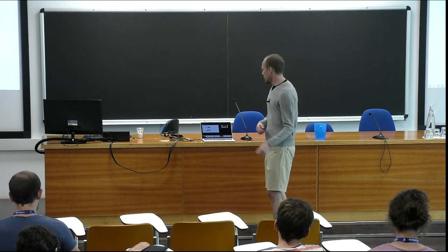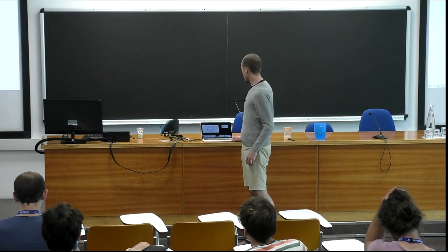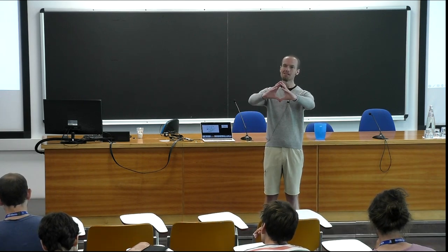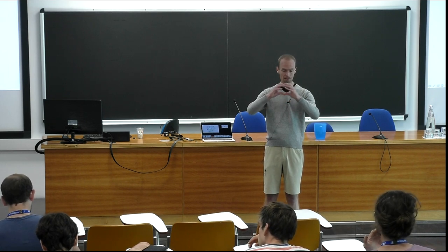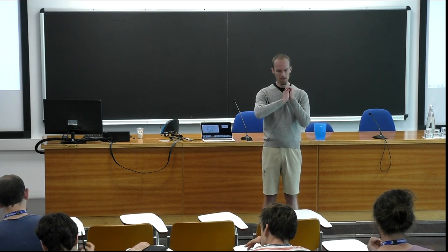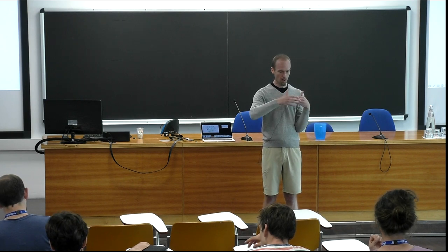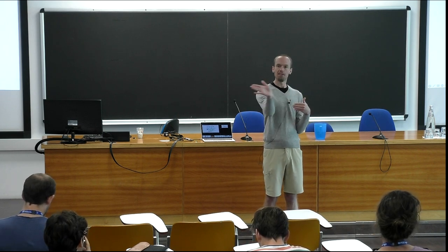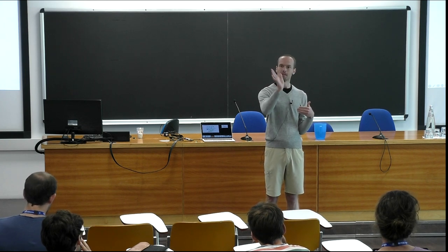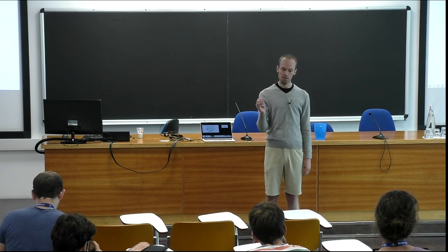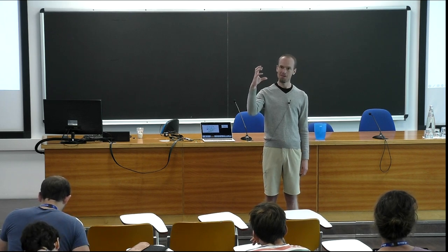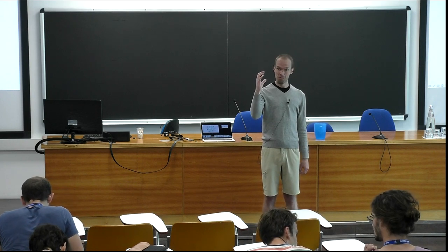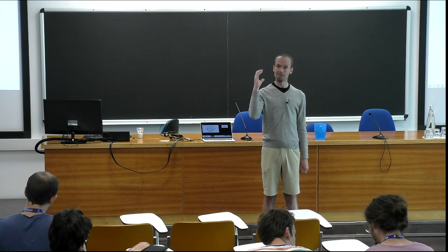Okay, so in this case, we've got what we call a magnetic sector instrument. We've got this stream of ions, and it's got everything in there. We take that stream of ions and accelerate them. We've got voltage accelerating the ions, and we've got a magnet. The ions take the corner at a different radius according to their mass. What we do with this instrument is position these little catcher's mitts, these Faraday cups, at what we think is the right radius. So you can put it in the wrong place and catch no ions.